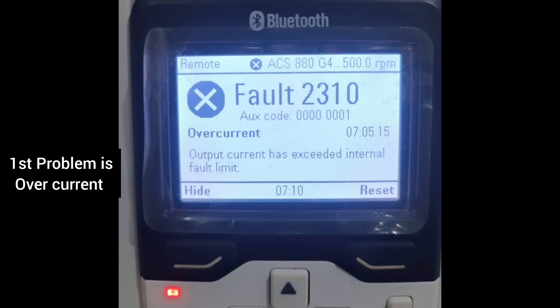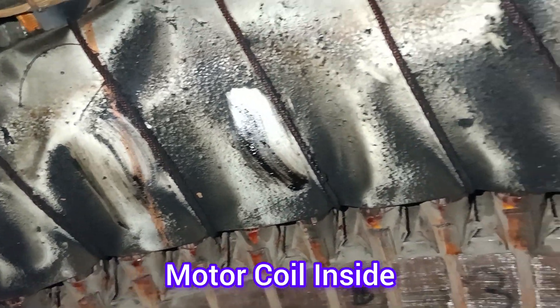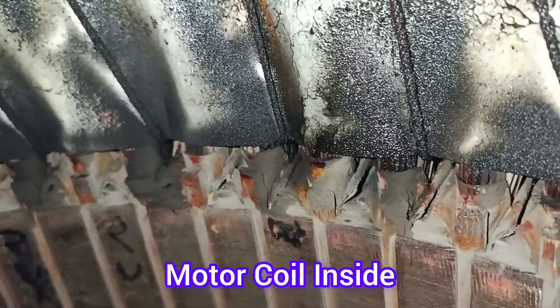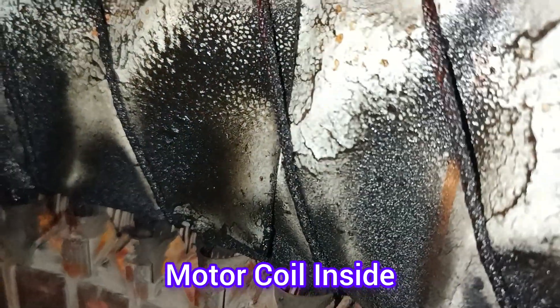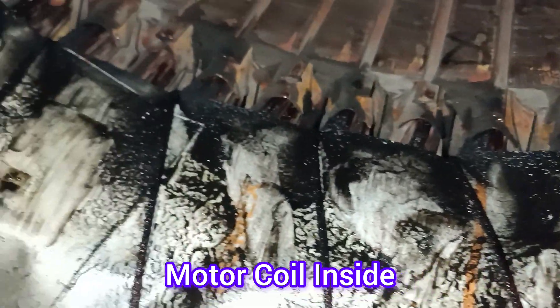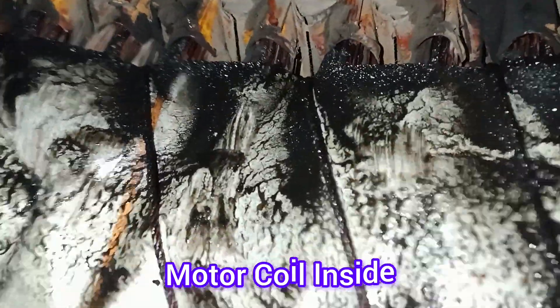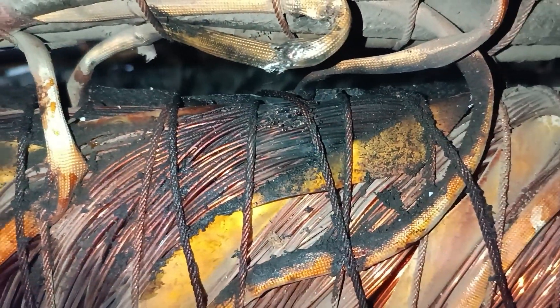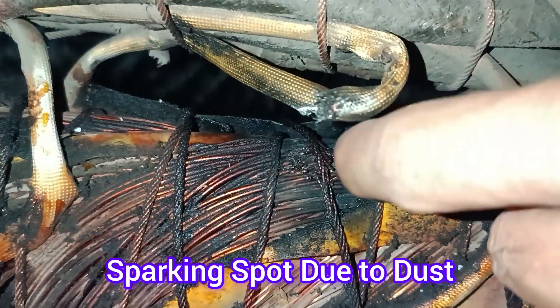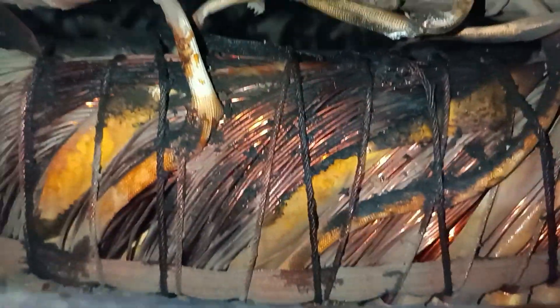Dear viewers, the first fault was 2310, that means overcurrent. You can see the picture when we open the motor — motor coil inside. Very clearly there is lots of dust inside the coil of this motor. The motor capacity is 360 kilowatt, a huge induction motor on three-phase supply, running via VFD brand ABB ACS 880. The sparking is due to the dust, and for that reason one coil is damaged.